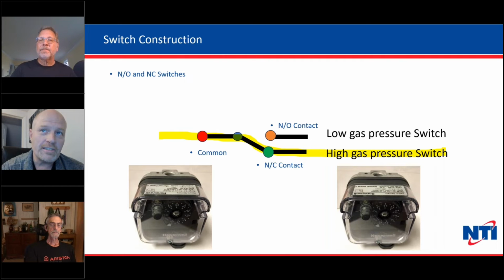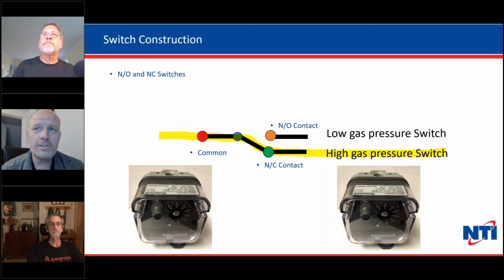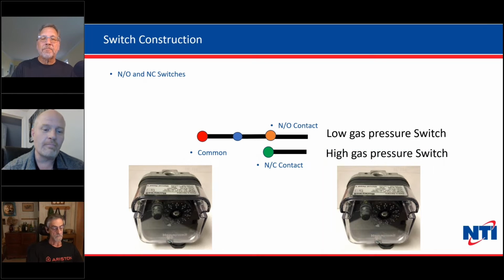And the reason that you're probably going to see it trip on just about every job is at some point you're going to be working, somebody's going to shut the gas off, or the inspector's going to shut it off. You're going to trip the switch. These ones are manual reset, so you do have to press the little button to reset them. So if you're doing a commercial boiler job and you start getting gas pressure switch errors, I'd say dollars to donuts, it's going to be the low pressure switch, and you just have to reset it and ensure that you've got good gas pressure, and your problem should go away.